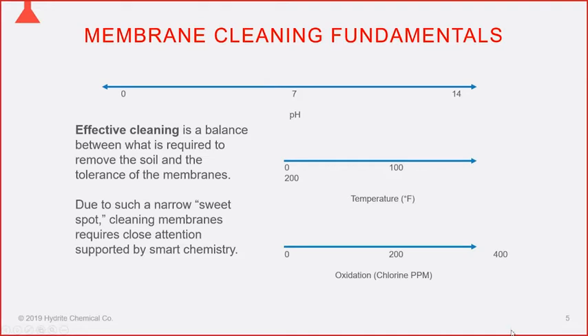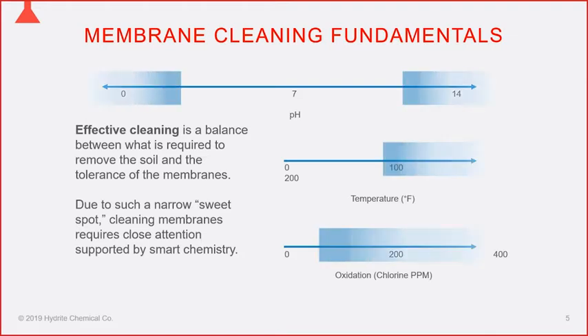For effective membrane cleaning, a balance is required. Like the four-by-four or five-by-five cleaning approach, the different cleaning factors all relate to one another: time, temperature, concentration, and mechanical action. Membrane systems are different in that they have very strict limitations of exposure to pH, temperature, and certain chemicals — especially oxidizers. There's a sweet spot we have to hit for effective cleaning.